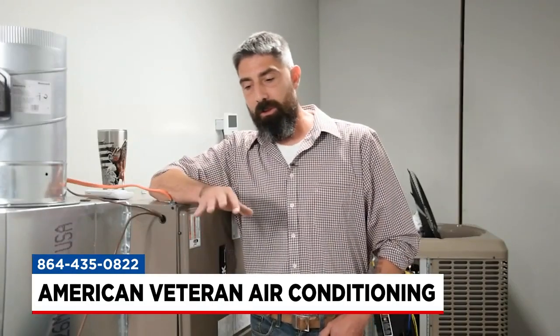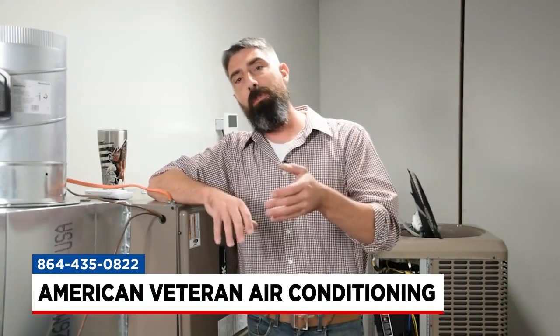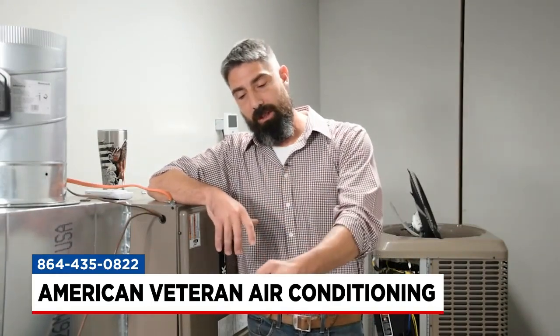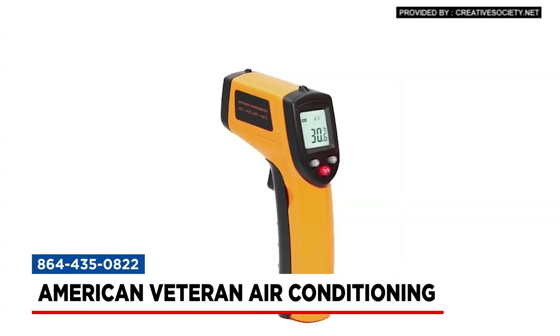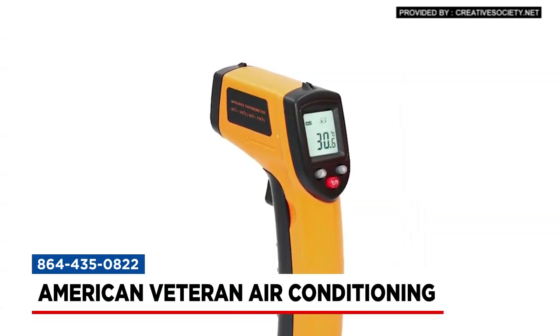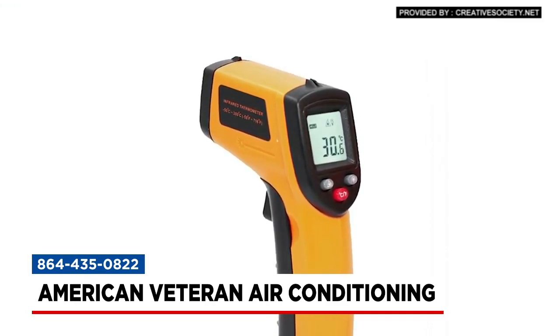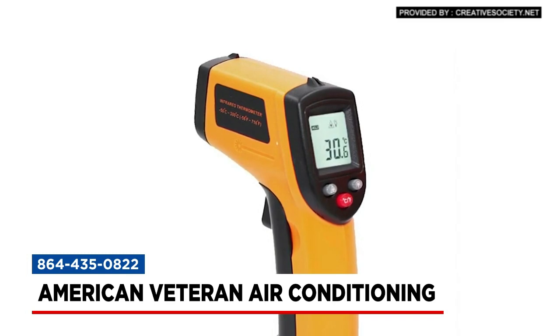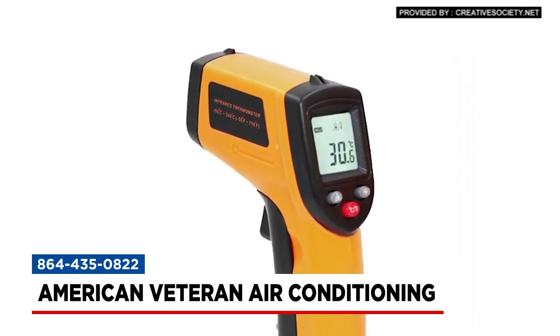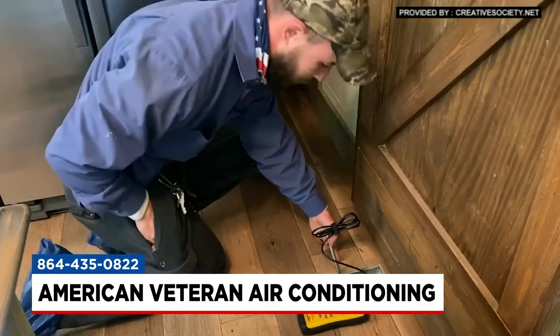There are a few things you can do if you suspect it in your home — like you've got a room that's not really cooling well. You can buy an infrared handheld thermometer, pretty cheap, like 15 or 20 bucks probably from Home Depot or something like that. If you suspect a problem, just check a temperature reading on all your vents. If you notice this one's at 55 but this one way over here is at 70, there's a good chance that air is not getting through that duct work.